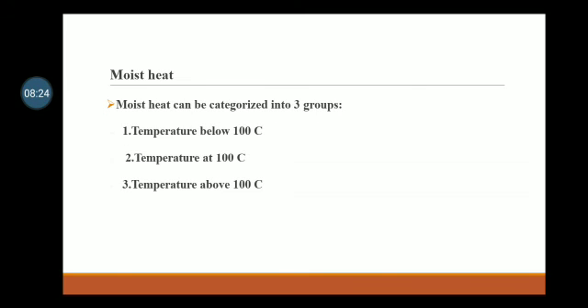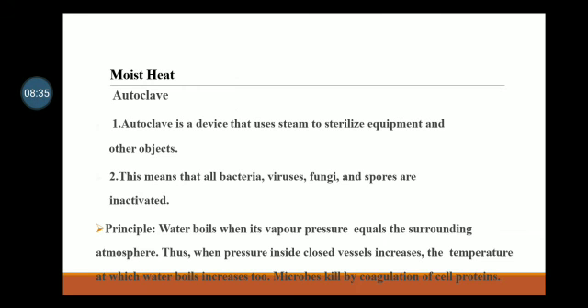Moist heat sterilization. Moist heat can be categorized into three groups: temperature below 100 degrees Celsius, temperature at 100 degrees Celsius, and temperature above 100 degrees Celsius. Autoclave is an instrument which is used in moist heat sterilization. An autoclave is a device that uses steam to sterilize equipment and other objects. This means that all bacteria, viruses, fungi, and spores are inactivated.